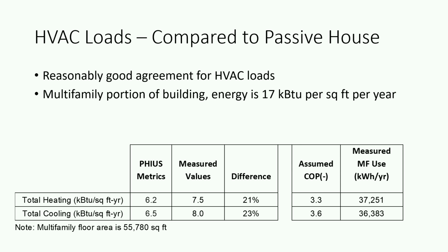Of course, we couldn't directly measure them. We only measured the energy use of the heat pump, but we used the inferred COP and the measured kilowatt hours to kind of back into what those loads were. So we basically showed that the heating and cooling loads were a little higher than the passive house tool predicted, but we were pretty close. And that means the loads were just extremely low.